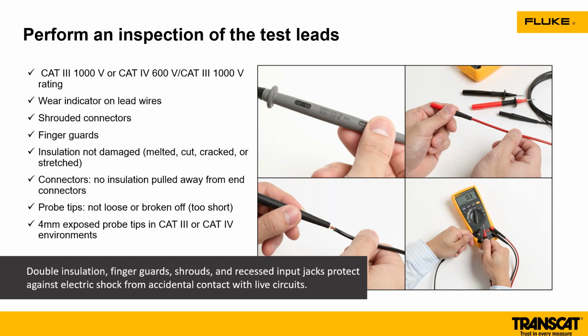So just double check, make sure that you have the right test leads for the right job. They should be rated. You should be able to see the category rating on your test leads. If your probes are broken, if you've got fraying on them, the insulation's pulling away, replace them. It's inexpensive, if you think about it. Even if the test leads were $50 a piece, that's still inexpensive compared to a hospital bill or a major incident that happened based on your test leads. So make sure you use the right test leads in your category environment.